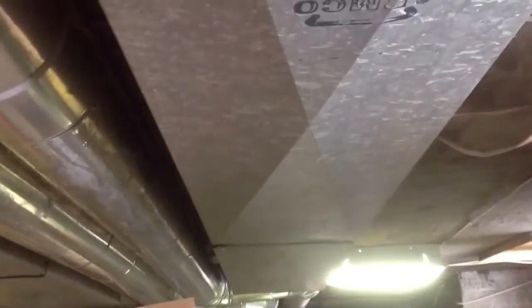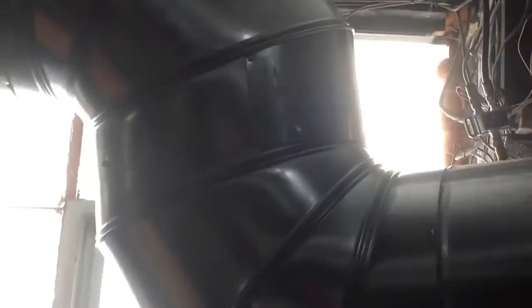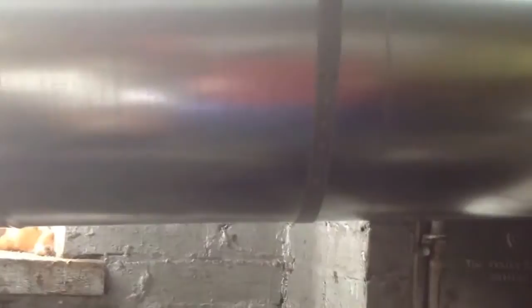I want to show you an alternative way to run some return air ductwork if your return air isn't big enough. So as you can see, this was our return air for 2 furnaces. 8 by 14 probably. So we needed more return air. So it was going to be very hard to run square ductwork over to the return. So what we did is we ran round ductwork from a return air that wasn't used anymore. And we ran it over here. I believe this is a 12-inch. And we ran it around back.